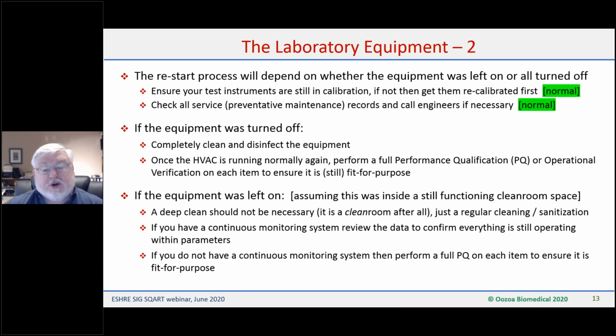If you have a continuous monitoring system, review the data to confirm everything is still operating within parameters. If you don't have a continuous monitoring system, then you have to run a full PQ on every piece of equipment to ensure it's still fit for purpose, that it hasn't drifted off calibration or whatever. So a lot more work. And again, this is why I think these continuous monitoring systems are such a great idea, because it's done automatically for you. And instead of you measuring it once, perhaps twice a day, it's logged every 5 minutes. So you have much more information on how the equipment is performing.